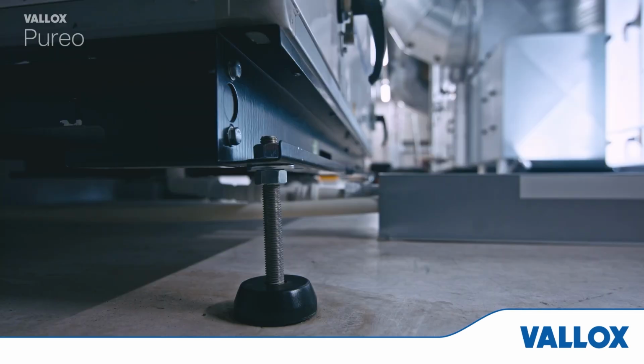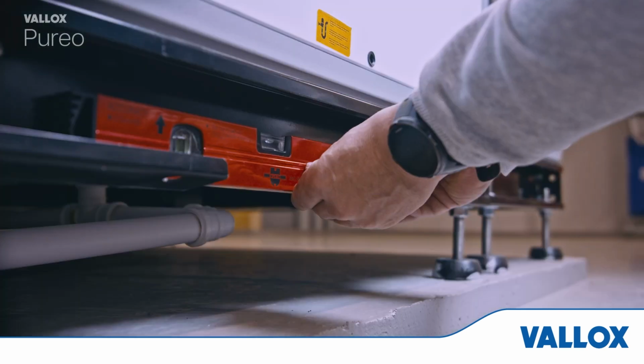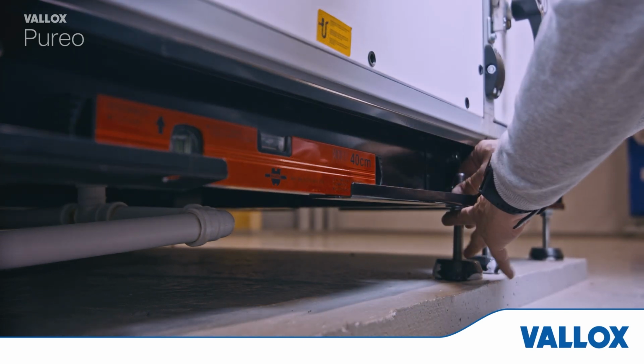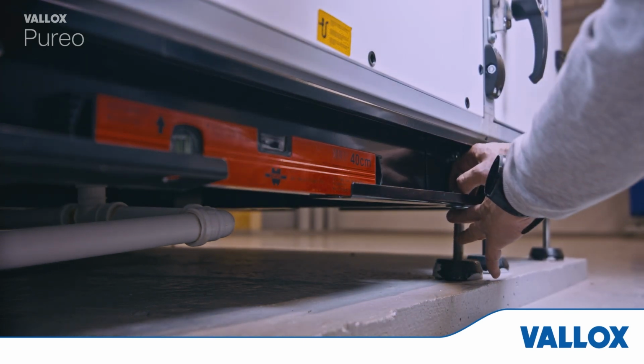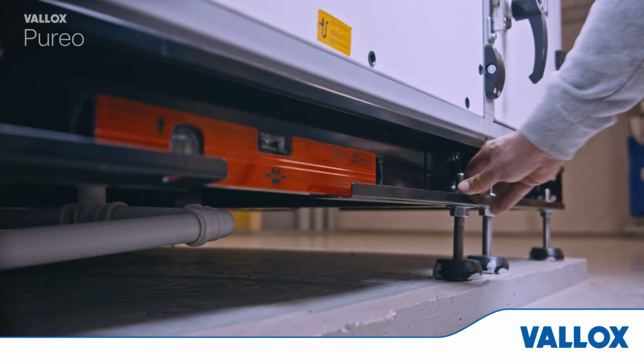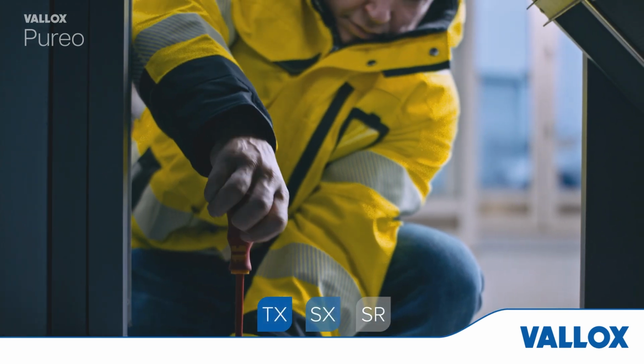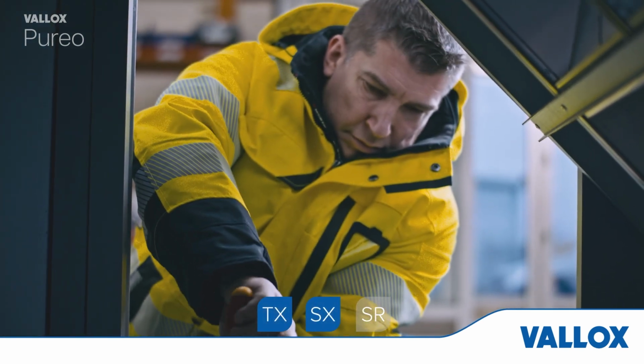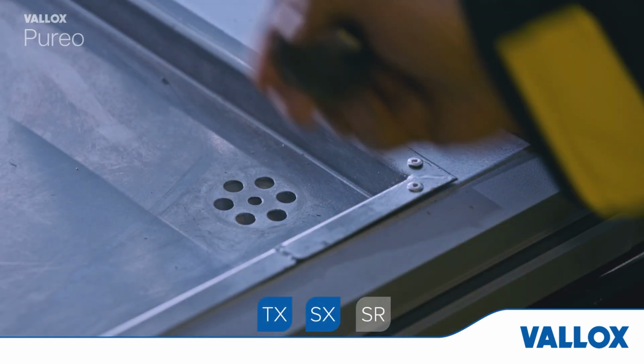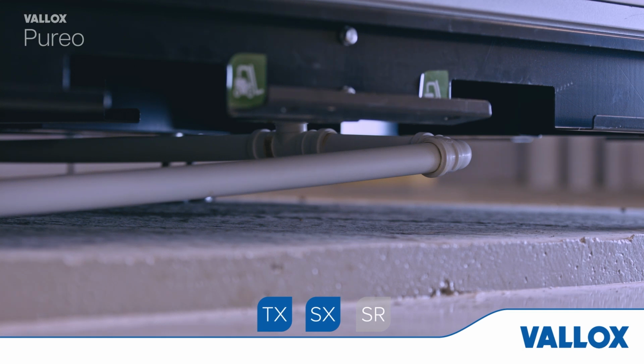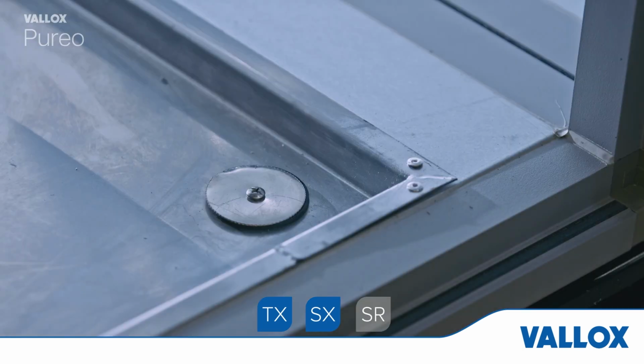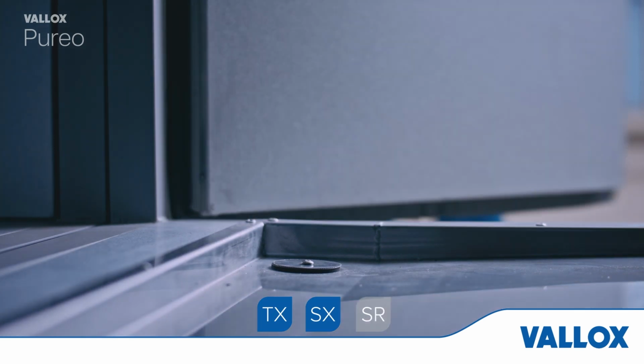Make sure that the floor can bear the unit's weight, and always install the unit horizontally. Use leveling mounts to stabilize the unit. Never install the unit without leveling mounts. When installing a TX or an SX unit, remove the drip pan plugs. Connect the condensing water tube to the openings and install optional siphons. Make sure that the unused condensing water drain holes have been plugged.